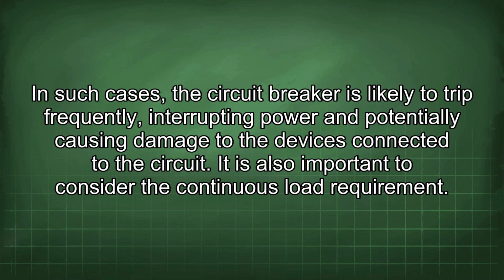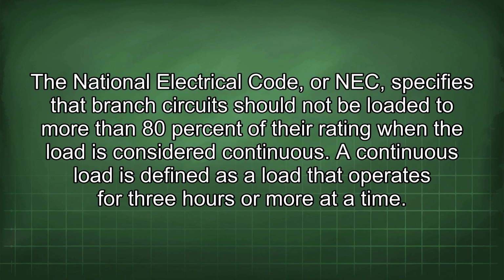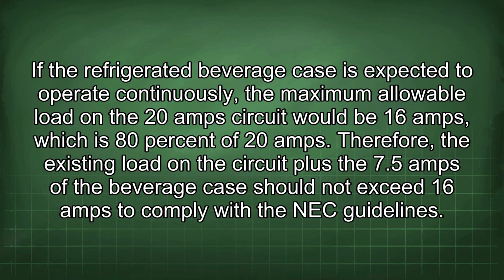It is also important to consider the continuous load requirement. The National Electrical Code, or NEC, specifies that branch circuits should not be loaded to more than 80% of their rating when the load is considered continuous. A continuous load is defined as a load that operates for 3 hours or more at a time. If the refrigerated beverage case is expected to operate continuously, the maximum allowable load on the 20 amp circuit would be 16 amps, which is 80% of 20 amps. Therefore, the existing load on the circuit plus the 7.5 amps of the beverage case should not exceed 16 amps to comply with the NEC guidelines.